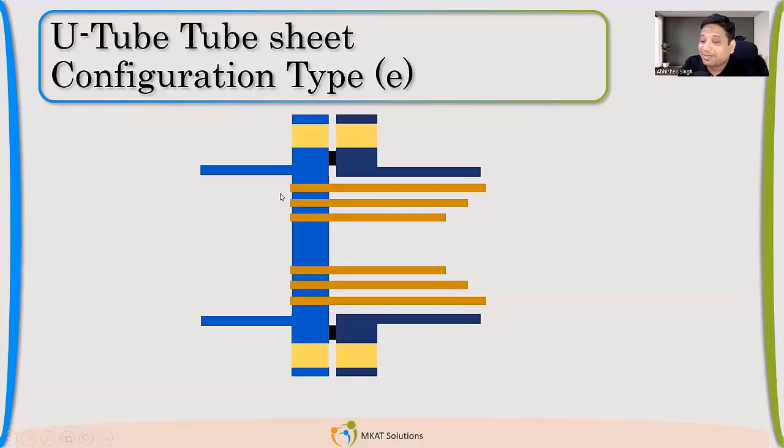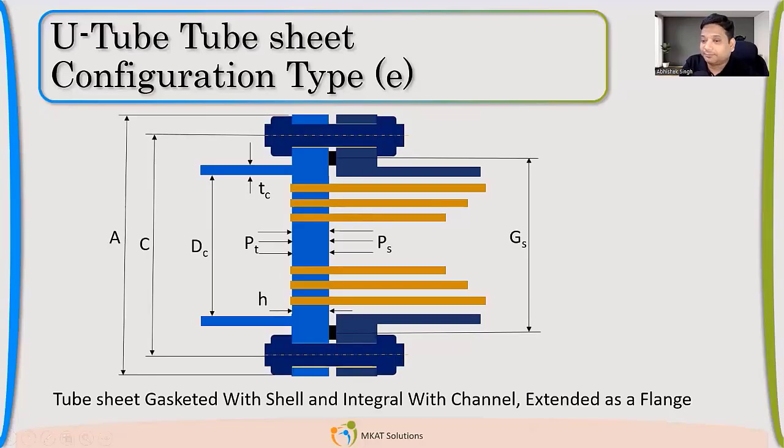This tube to tube sheet area will completely become blind. So if we are using a bolted connection, we'll be able to access it, right? So we can clean, we can replace tubes. If it is a U-tube, it is not possible to replace, but at least we can do plugging. So all this is logic, nothing trivial.